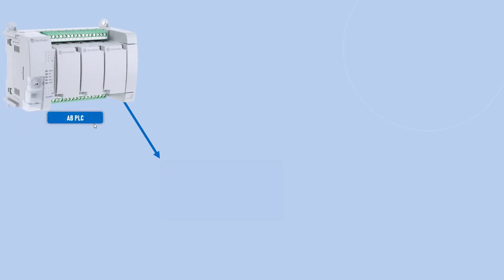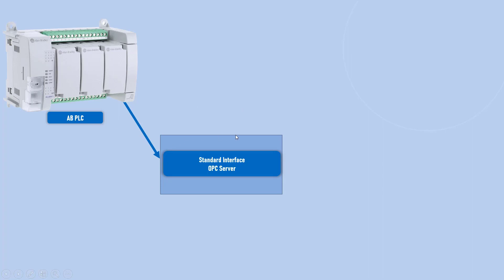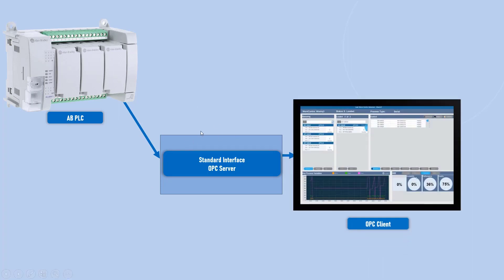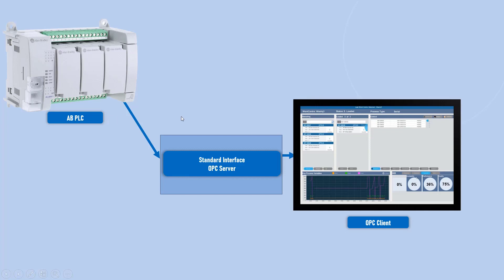we got OPC DA. In OPC DA, now you got a standard interface, which is your OPC server. If you got that and if your OPC client, which is your HMI, supports that OPC, if your Allen Bradley PLC also supports that, you don't need to worry about the drivers in order to communicate with Allen Bradley PLC. Rather, you are relying on a standard technology OPC.